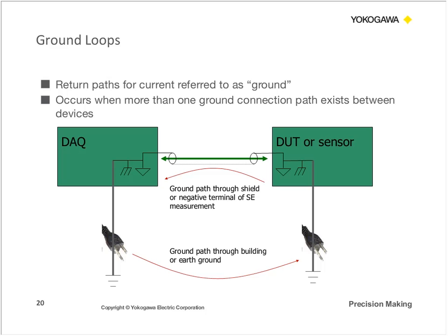So this is communications cable or measurement cable. You want to make sure that you're not connecting the grounds internally between the two systems, because if you do that, you're going to create a ground loop. And what happens when you have a ground loop is, let's say, for example, the power shuts off or a lightning strike occurs, and you have these transient voltages that occur. Well, the transient voltage is going to cause that 1 volt difference between the two receptacles. It may now jump up to several hundred or even several thousand volts across the instrument, and that's going to end up damaging both the instrument as well as the test cell environment.